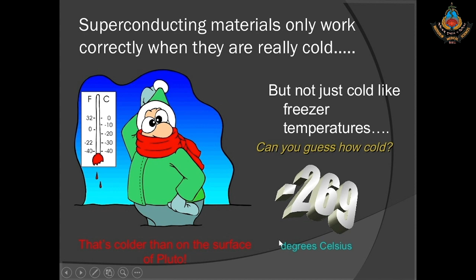This seems like a really easy way to create a strong magnetic field, but these superconducting coil materials only work correctly when they are really cold, not just like a freezer, but minus 269 degrees centigrade, as cold as Pluto. With the patient safety check complete, the scan can begin when the part of the body to be scanned is placed inside the center of the primary magnet. The magnetic field produced is very steady and strong. This field causes hydrogen nuclei of the patient to line up in a particular direction inside the magnetic field.